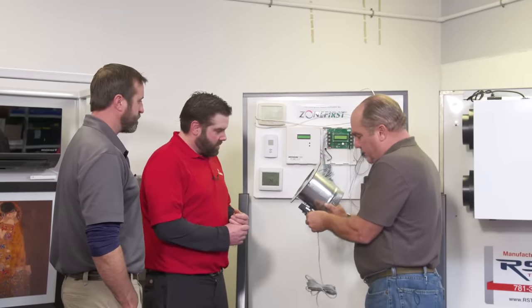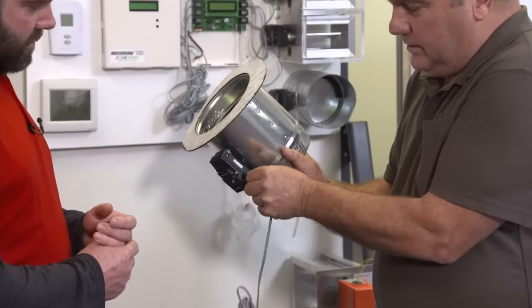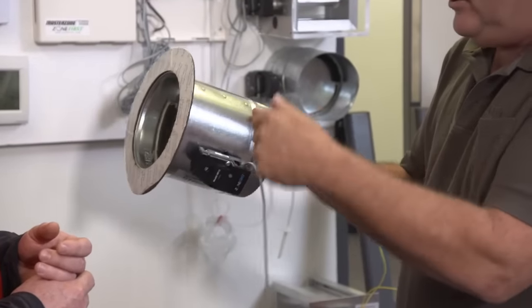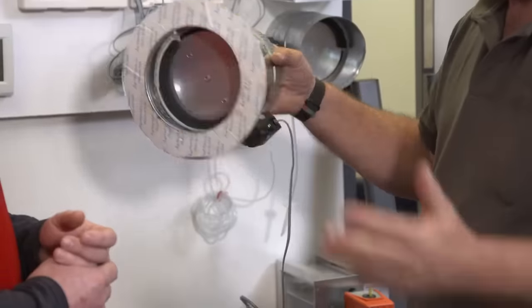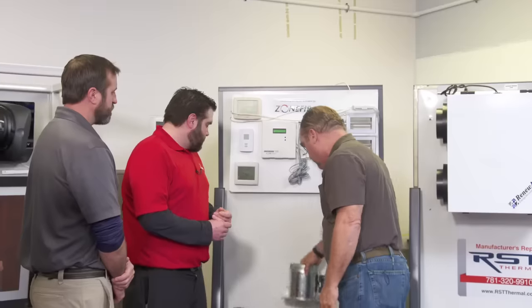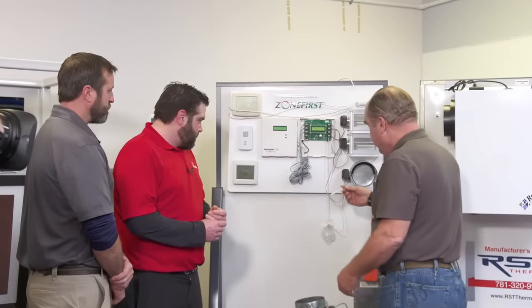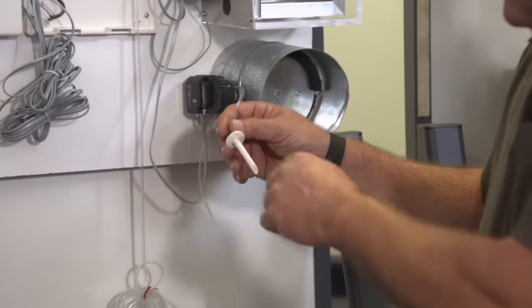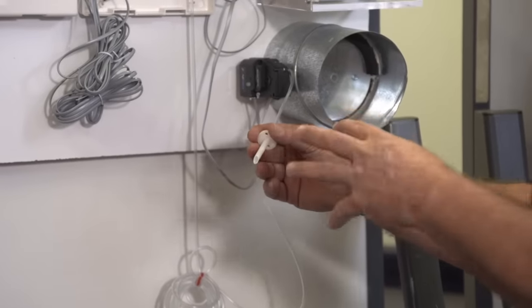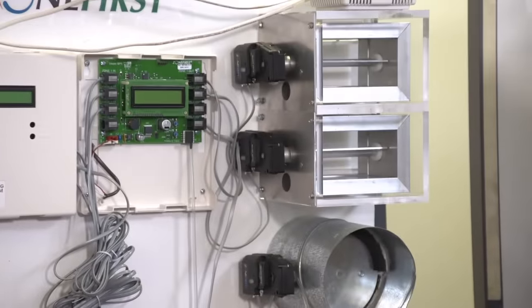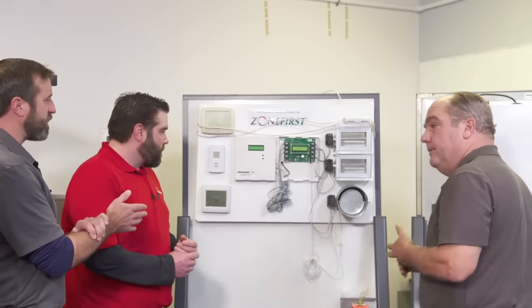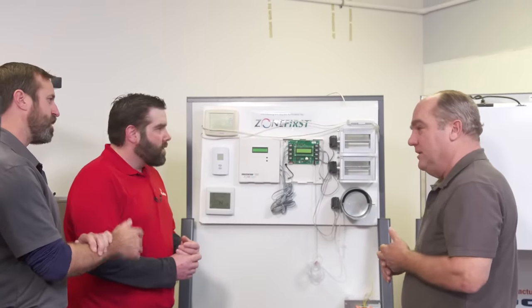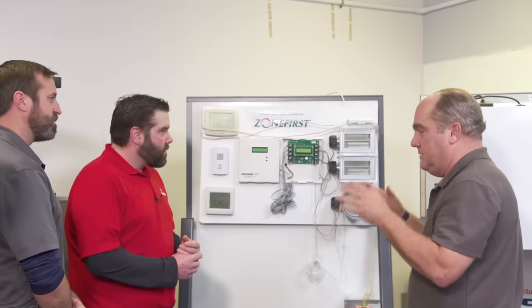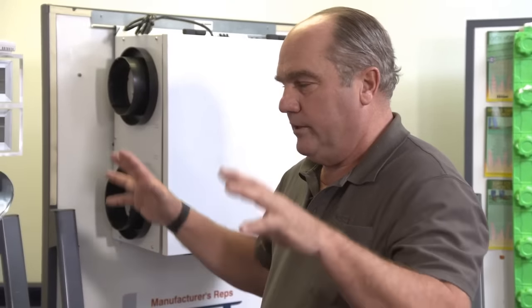This has a telephone jack here, so you can put these in, and then daisy chain one to another, and you can actually change the grouping later on. They have some retrofit options which are unbelievable. I love this thing instead of having a bypass damper, that dump zone. You stick this in the supply plenum, and it feels the pressure and opens up, so you don't need a bypass, which is totally cool. It will just slightly open another zone or two to compensate, just bleed off just enough. It's really nice because you often don't have enough room for a bypass anyway.